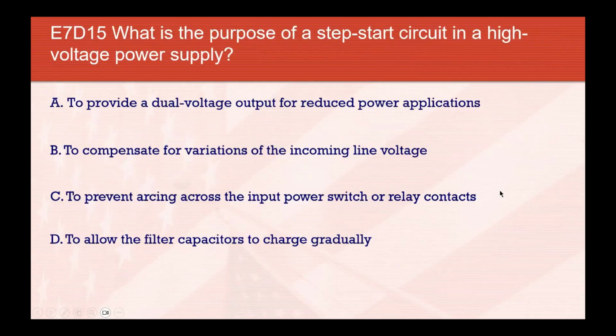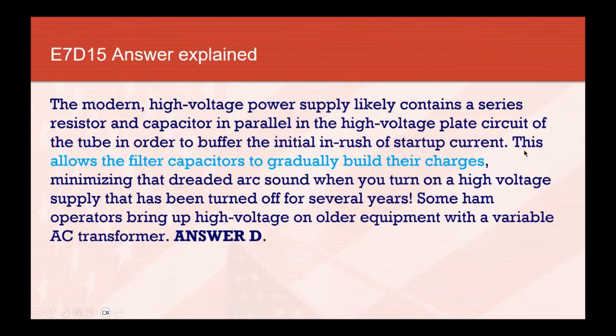The purpose of the step start circuit in a high voltage power supply: so we don't hit those capacitors with all we've got at one time and cause arcing. We don't want the arcing. We want the filter capacitors to charge up gradually so we don't blow them up and arc across them. Otherwise, they would act as a dead short when we first got the inrush of current.